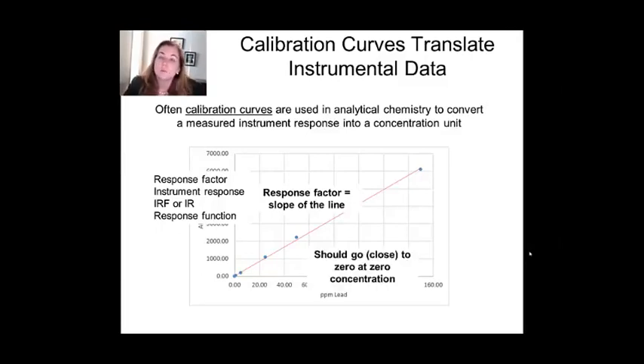You want your calibration curves to be close to zero at zero, with one important exception we'll see later this week, which is in the method of standard additions. Because that basically says you have no offset in your data. Now you can sort of live with an offset, but generally speaking, it's not a good thing if your instrument has too much of one. You're going to want the calibration curve to be linear. Every instrument, if you signal too much material in, will eventually flatten out. You put more stuff in and you saturate your detector. It can't measure anymore. You might break it if it's a photo detector. So you want to be in the linear range. And you're going to evaluate that by looking at the R squared, which is a statistical parameter about the linearity of the plot. And sometimes they don't look as pretty as this. Sometimes you can have very noisy calibration curves, and that just translates into error in what you do with them. But what you want to be on the lookout for are curves that are just simply not linear.